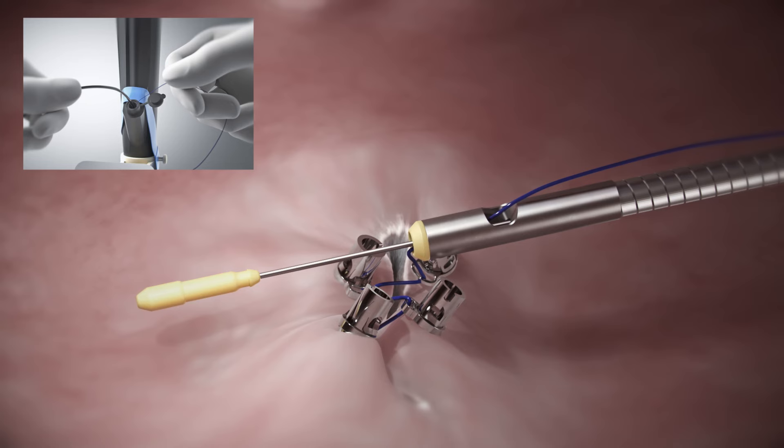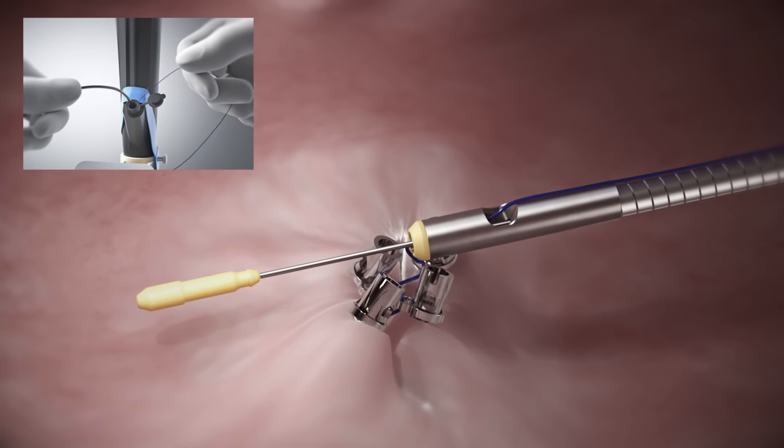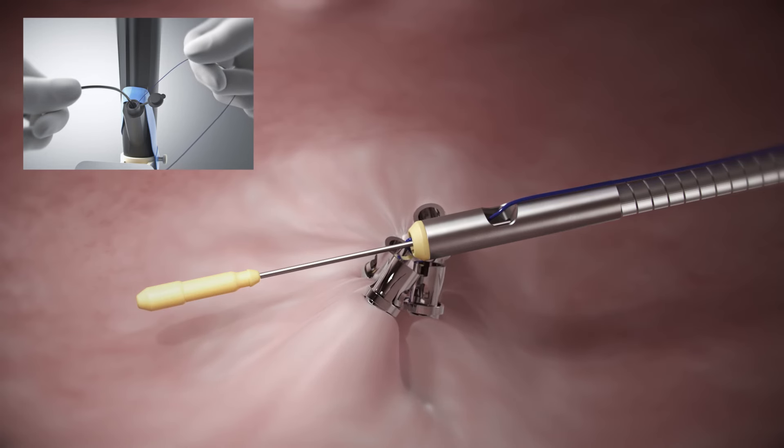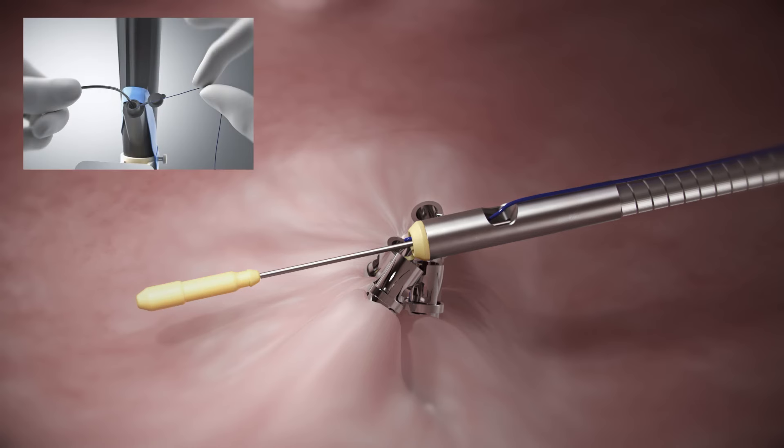While holding the cinch catheter in place, apply tension to the suture until the helix tacks and tissue have been approximated. Care should be taken not to pull the suture too tight, resulting in breakage. Prior to deploying the cinch, hold suture tension gently, grasping between thumb and pointer finger, allowing the suture to slide.